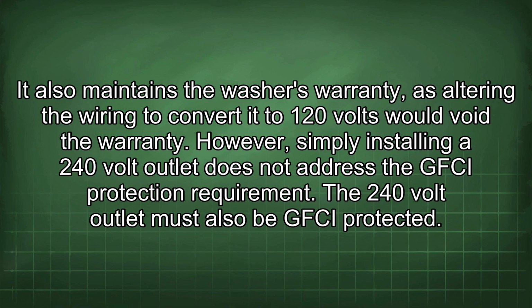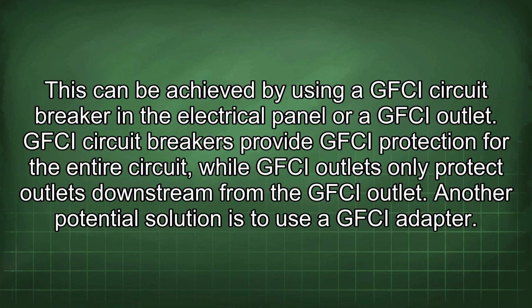However, simply installing a 240 volt outlet does not address the GFCI protection requirement. The 240 volt outlet must also be GFCI protected. This can be achieved by using a GFCI circuit breaker in the electrical panel or a GFCI outlet. GFCI circuit breakers provide GFCI protection for the entire circuit, while GFCI outlets only protect outlets downstream from the GFCI outlet. Another potential solution is to use a GFCI adapter.